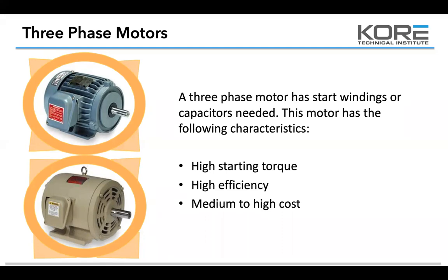So they have a really high starting torque, they're high efficiency, and they're medium to high cost. Anytime you're getting into three-phase motors, because they are high efficiency and because of the way that they're wound, they usually are pretty costly, but they're my preferred application. Anytime we can use a three-phase motor, we're going to get a little bit of freedom. We're going to have less component failure. As long as we get good voltage to that motor and we take care of the bearings, if there's grease zerks on the motor or whatever, that motor is going to last a long time.